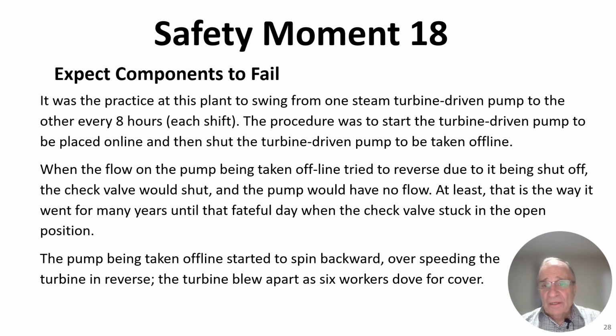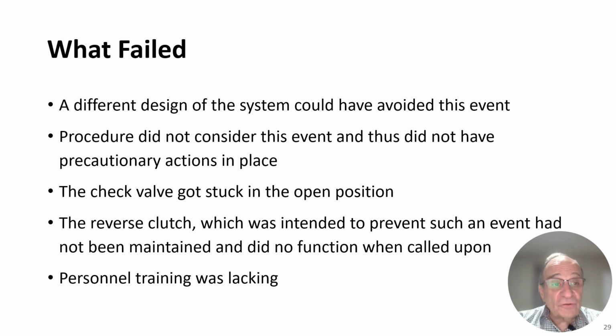Now, the pump that was taken offline would automatically stop pumping and the flow would try to go backwards through the pump. However, there was a check valve that would prevent that from happening. At least that's the way it was designed. When the flow on the pump being taken offline tried to reverse due to it being shut off, the check valve would shut and the pump would have no flow. That's the way it was designed, and that's the way it worked for many years, until that fateful day when the check valve stuck in the open position. The pump being taken offline started to spin backwards, overspeeding the turbine in reverse. The turbine blew apart as 6 workers dove for cover. Fortunately, no one was killed or injured.